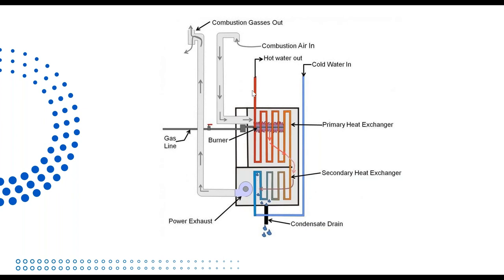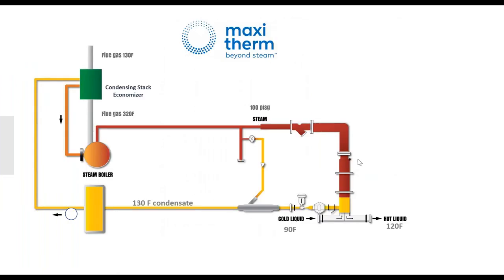So it can't be 140 if it's 120 set point. So let's apply this to a flooding design. Let's say we have a set point of 120 Fahrenheit with a return at 90 Fahrenheit. We can oversize the heat exchanger so that condensate at full load will come out at 130 Fahrenheit.